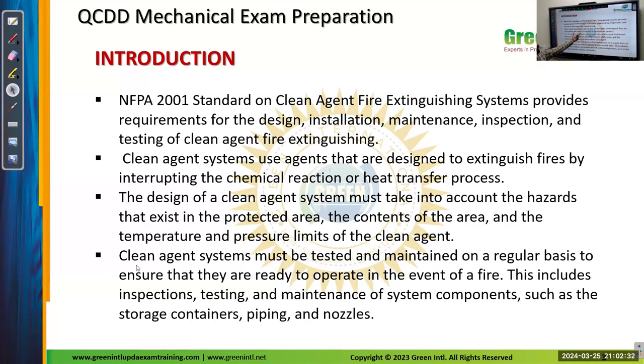These systems extinguish fire by interrupting the chemical reaction or the heat transfer process. We have seen the triangle, right? In the triangle, oxygen, heat, and fuel are there. It will create a chemical reaction. So what it will remove is heat. It will take out the heat, so that will remove the chemical reaction in that system. In portable fire extinguishers, it will take the oxygen or heat. So in this type of fire extinguishing system, it will take the heat transfer from the system. If you remove any one of these three, the fire will die. Fuel and heat. Yes.